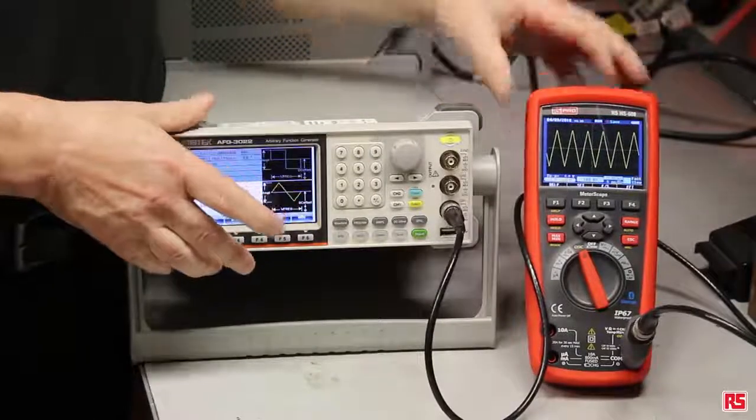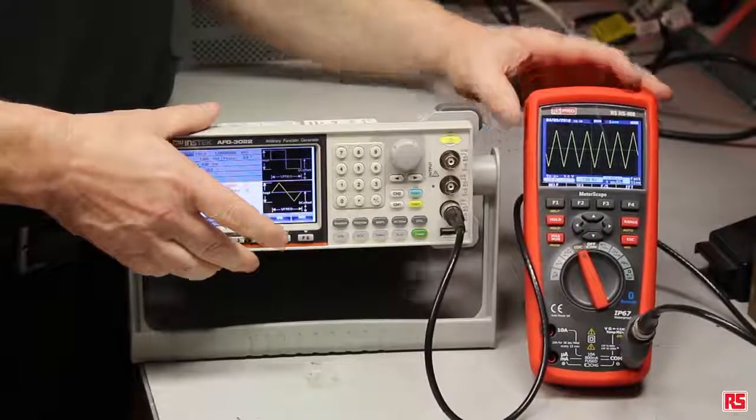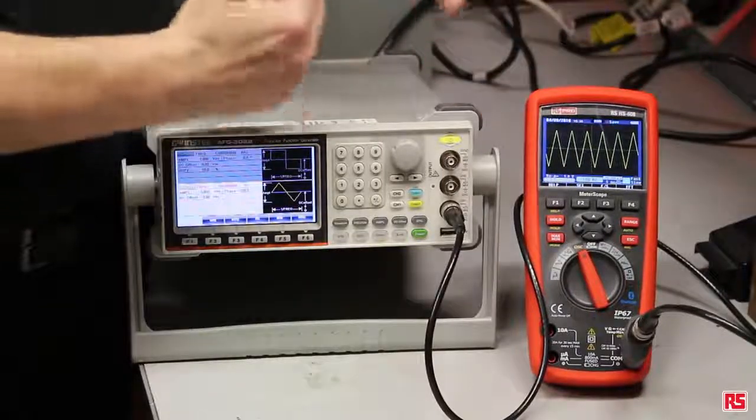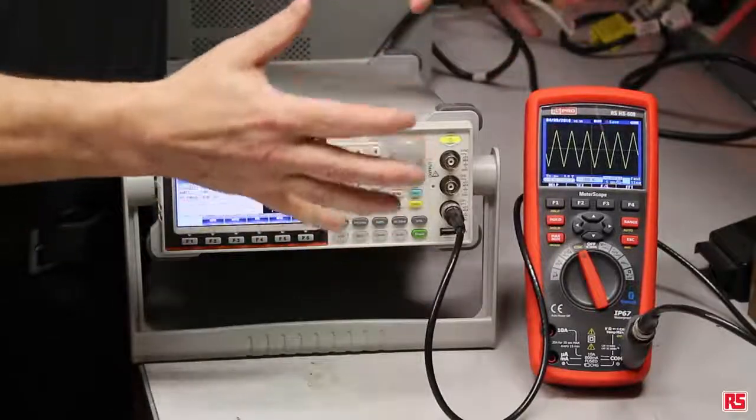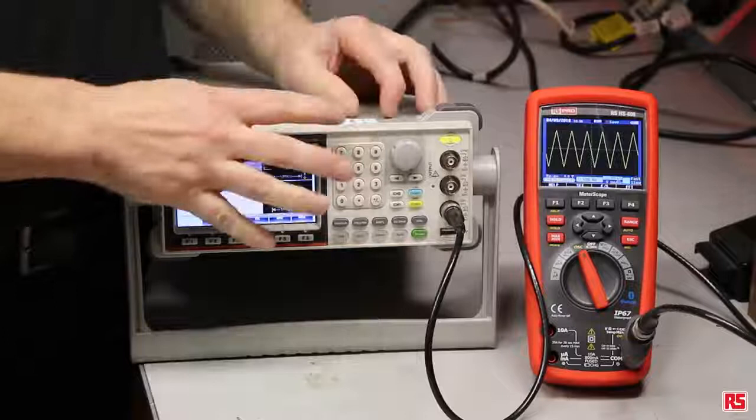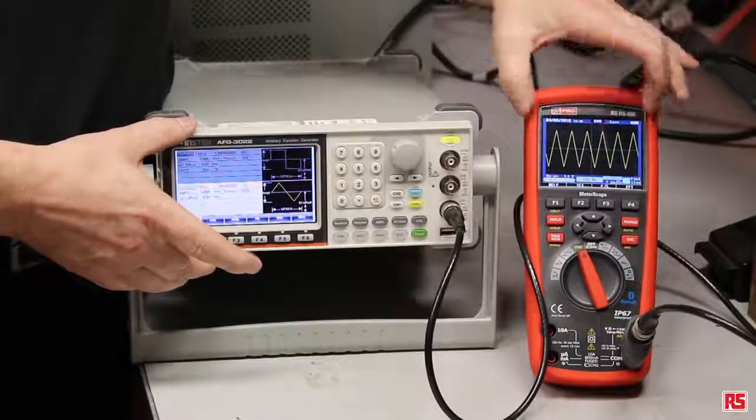So there are a few other things you can do on here. You can measure the noise, you can measure the harmonic rate as well. So you can look at the different harmonics within the waveform, something quite detailed like that on a digital multimeter.